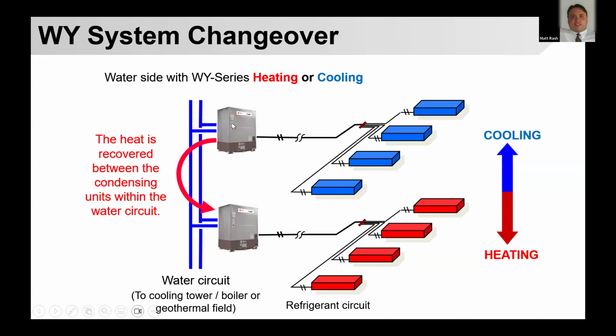Also on the building side, within that building condenser water loop, you're exchanging, rejecting, transferring heat among the modules in the building across that common loop. So that's your common kind of highway exchange system for heat recovery. With the changeover system, all of the individual fan coils on the respective module have to be in the same mode at the same time.